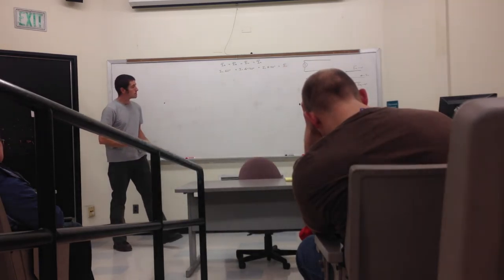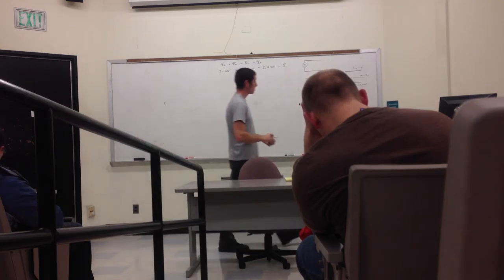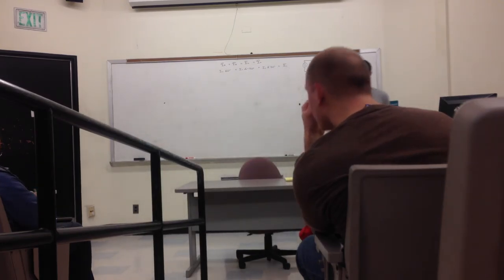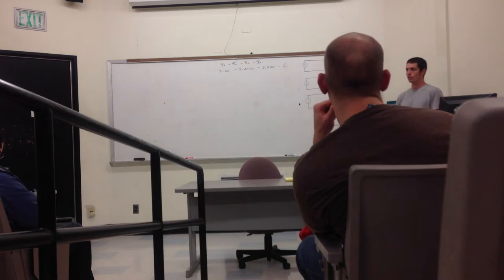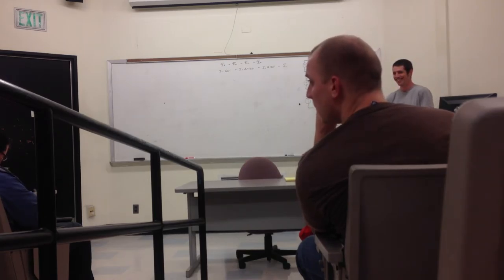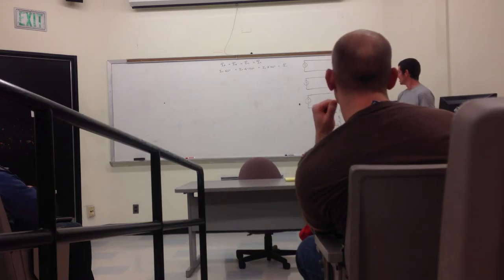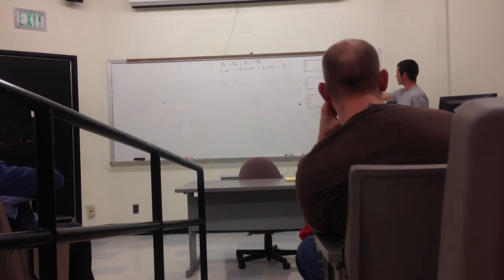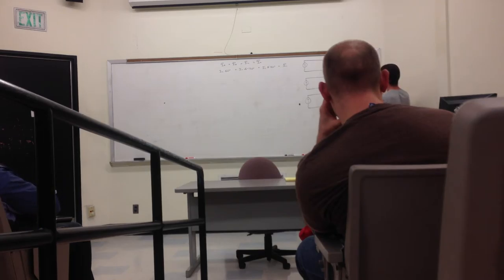Question about the, we always assume it's a balanced load, but what if there's a fault condition, and then all of a sudden you do need that neutral line? You don't, even in that case, the currents just flow, everything goes down. If you have a fault here without the neutral, your fault currents are going to pull in from the other two lines.